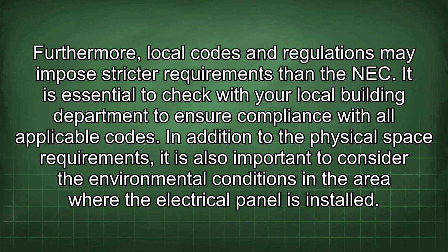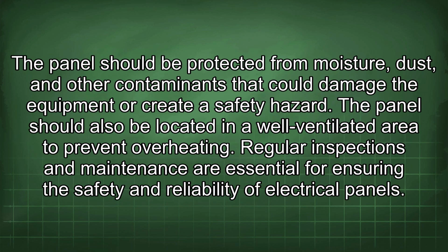In addition to the physical space requirements, it is also important to consider the environmental conditions in the area where the electrical panel is installed. The panel should be protected from moisture, dust, and other contaminants that could damage the equipment or create a safety hazard. The panel should also be located in a well-ventilated area to prevent overheating.